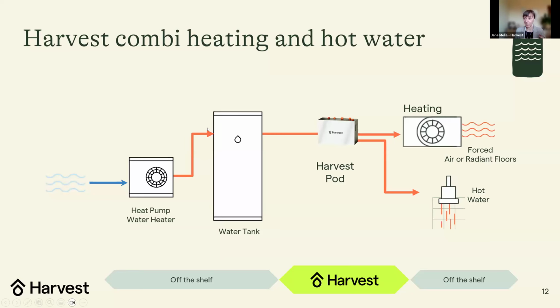That heat's going to be stored as hot water in a tank and then delivered through a hydronic air handler or radiant floors to your home. That tank is the battery. We're using a stratified tank, hot water floats, so you get hot water at the top, cold water at the bottom. That means it's very modular. In the winter, we may heat the whole tank twice and have about the same energy capacity as, say, a conventional Tesla Powerwall or other lithium-ion battery. But in the spring and summer, we may only heat half of it, and in summer, maybe just a quarter. So very modular, so you're not wasting any energy, basically fully decoupling heat pump operation from heating delivery to allow you to maximize efficiency and minimize your bills.